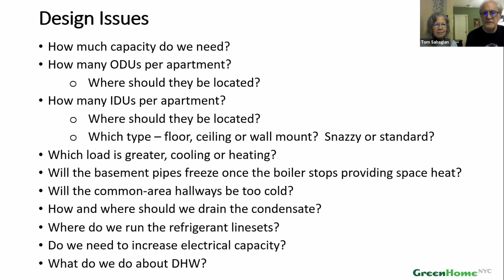One interesting thing — originally I thought that if we used 2 outdoor units per apartment, putting one toward the front of the building in these air shafts and one in the back, where we ended up putting a lot of them anyway, that would reduce the line set length, diversify the system a bit, and reduce the amount of demo we had to do in the apartments.